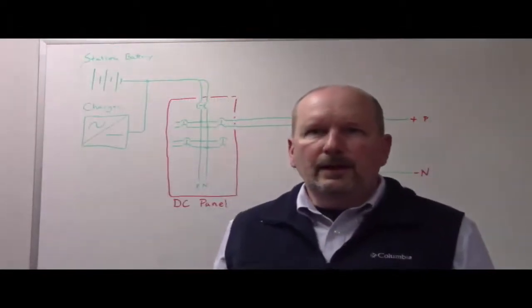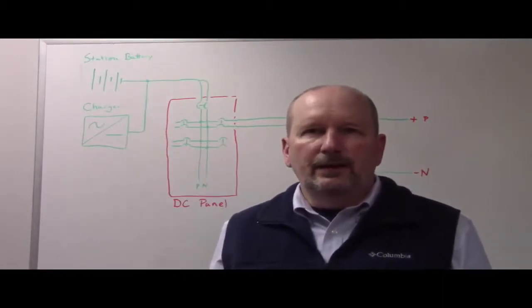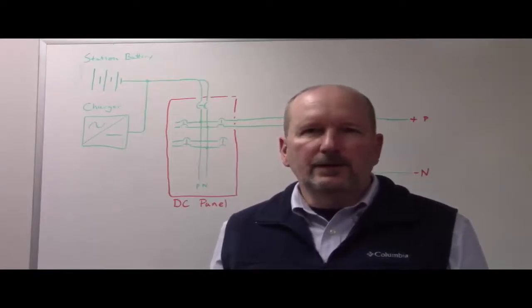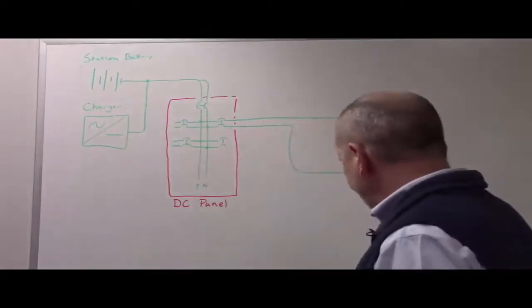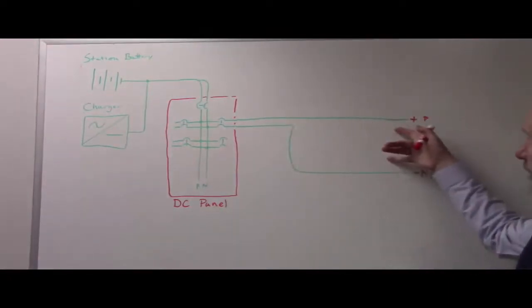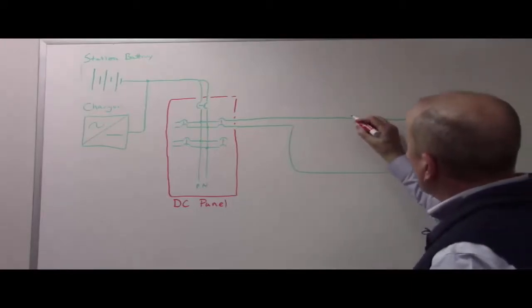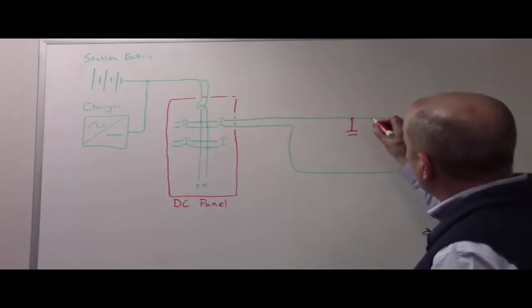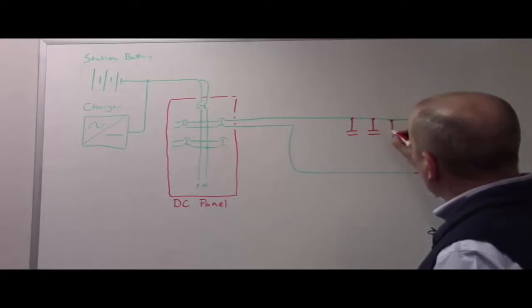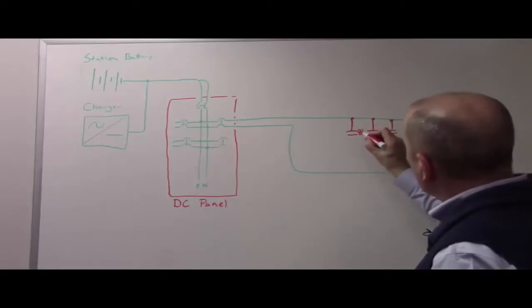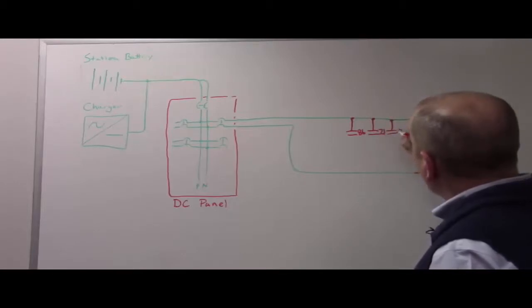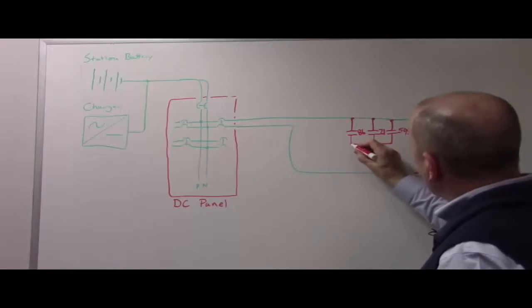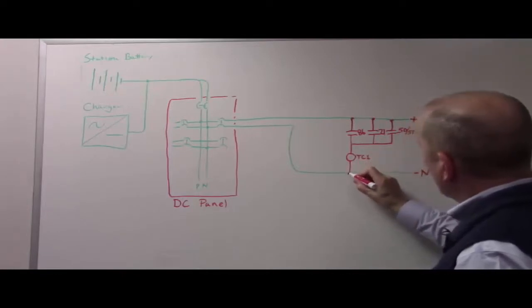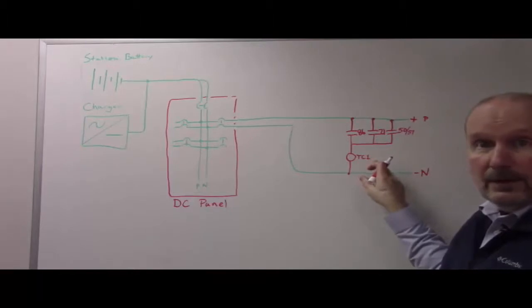Okay, I'd like now to give you an example, which I've already alluded to, of how we can implement some interesting logic for a circuit or for a substation. I'm going to take our drawing where we established a control voltage, and I'm going to draw in it a couple of contacts in parallel. And so that would be OR logic. I'll go with three of them. We'll label the first one 86, the second one 21, the third one 50/51. And this could be any kind of circuit breaker, and then we'll put here trip coil 1. So if we energize trip coil 1, what's going to happen is you're going to trip your breaker.